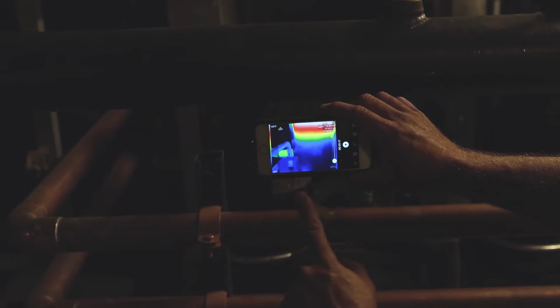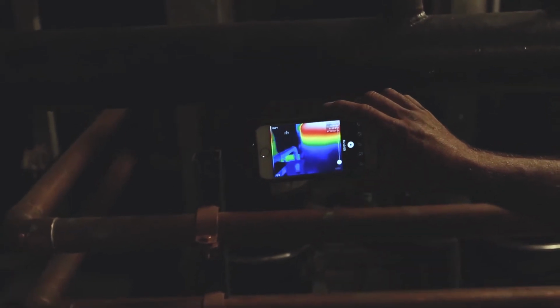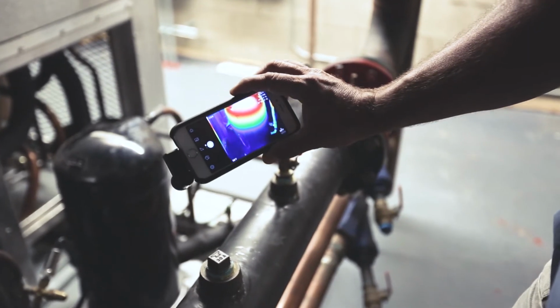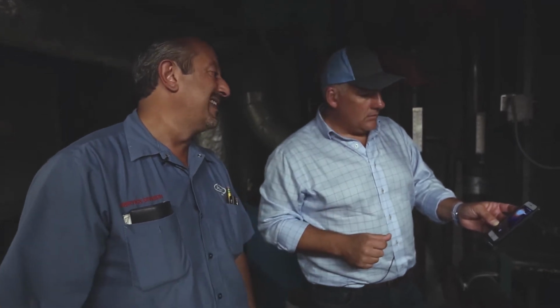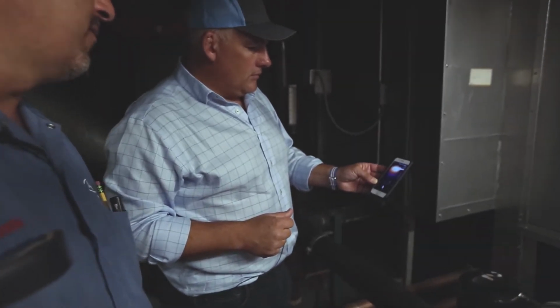If you have internal issues with the compressor, you can see them through the actual equipment. If there's a mechanical issue inside the compressor though, and you don't have a nice even ring, that tells you there may be a mechanical problem. Maybe the seals, a rotor possibly leaking, or an internal problem. Thermal scan will help you resolve your problem with it. Nice, that's good to know, okay.